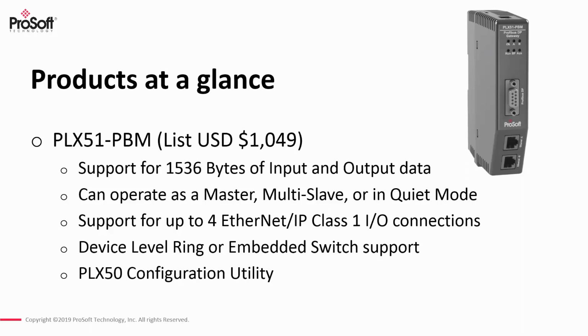Also, we took advantage of being able to support multiple Ethernet IP Class 1 I/O connections. So back to an Ethernet IP device, we can now support multiple I/O connections through there. So your data transfer back to the PLC is much faster. You don't have to worry about paging of data, and you can get data I/O updates of up to 10 milliseconds into an Ethernet IP Class 1 I/O connection.